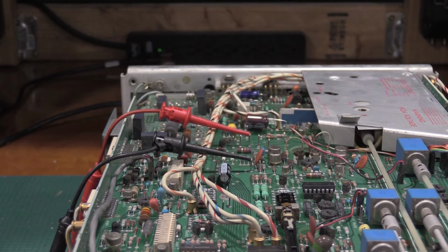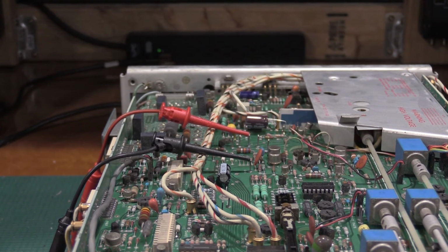So that's good. Let's bring this down to 104. Give the meter 2 cycles to catch up. That's actually in really good shape. It's still 55.01, so it didn't even change when I brought the voltage down. Let me switch this over to AC. And we're still good on the ripple on the power supply. So I'm going to check the ripple here real quick on everything. So that's 55. That one's good.